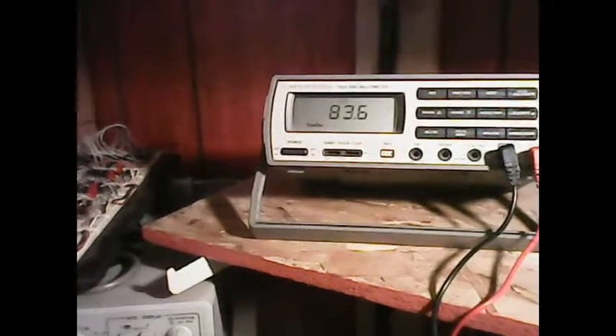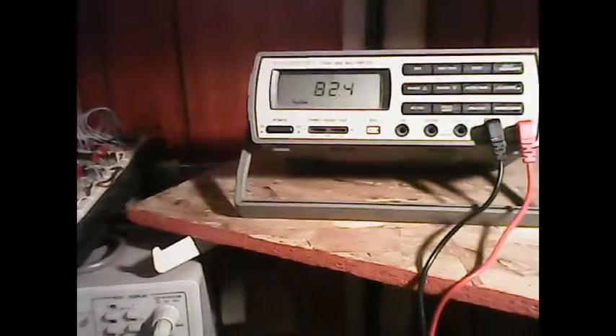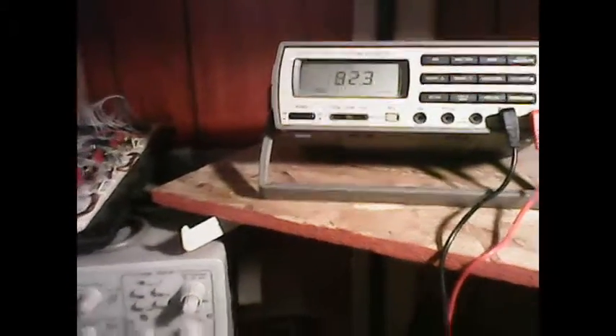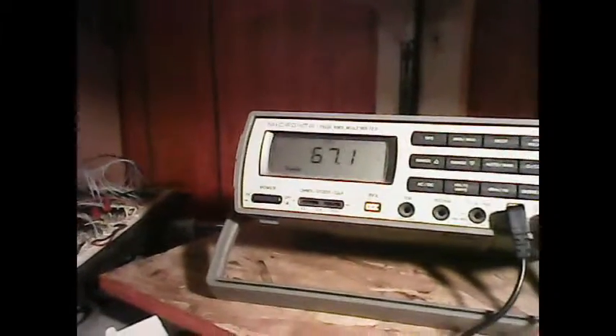Let's check the voltage out of the supply - 83, 82 volts, okay, so we're within a good range there. Now, if I'm at 68 volts across the motor, one more check - let's make sure this is tracking, how close are we tracking now? So again we check it here - 68 volts, 67, so we're within the range of 60 some volts.